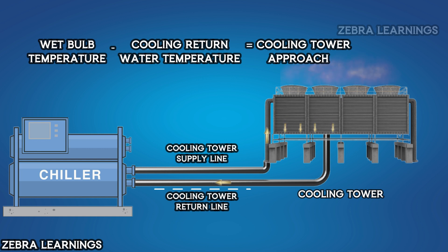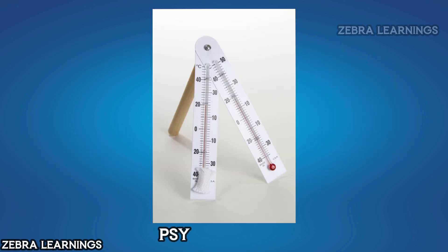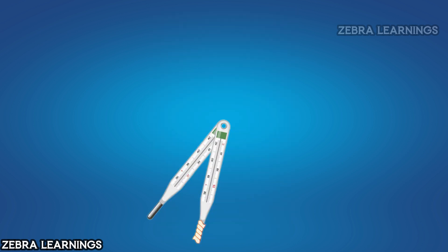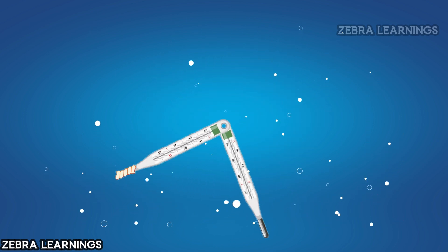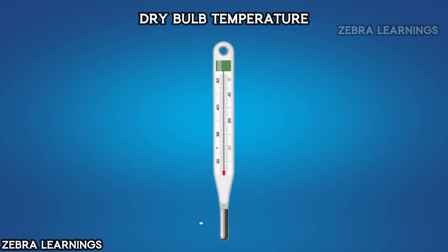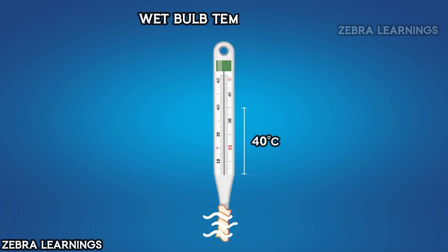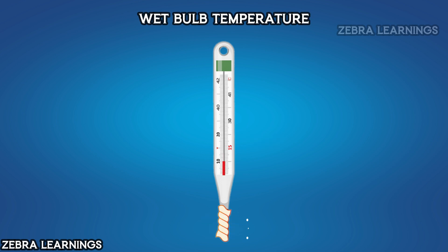Now let's see how to measure wet bulb temperature using a psychrometer. Take a psychrometer that has two thermometers. Wrap a wet cloth around the bulb of one thermometer and leave the other thermometer dry. When you rotate the psychrometer, all the heat in the air is transferred to the bulb. The mercury in the bulb expands according to the heat, and we can measure the temperature by how far it expands. In the wet bulb, the heat from the air is also transferred to the bulb, causing the mercury to expand.